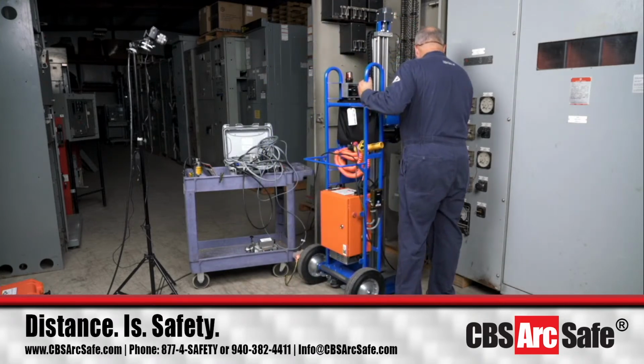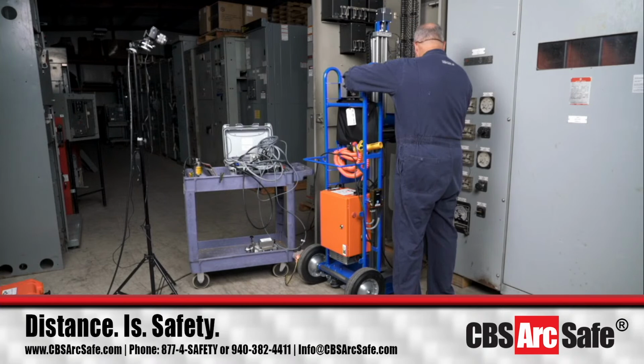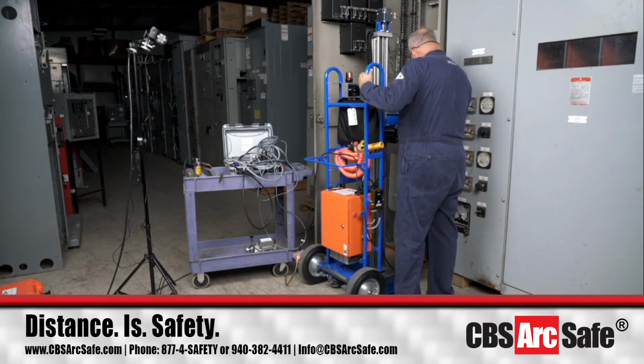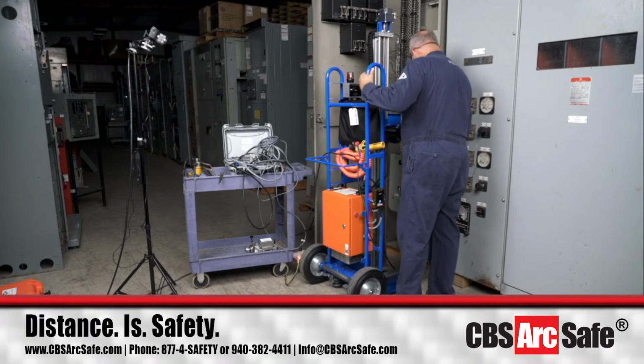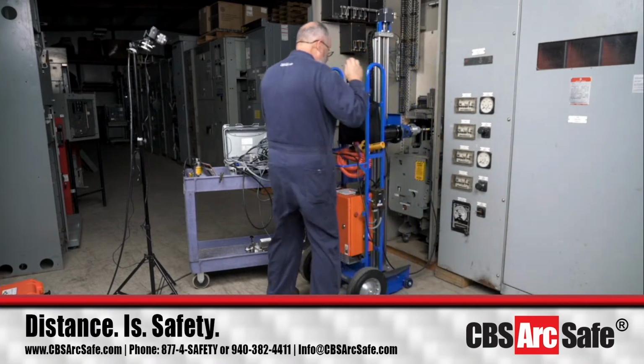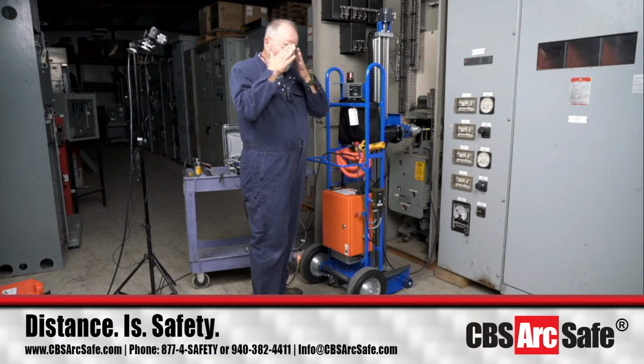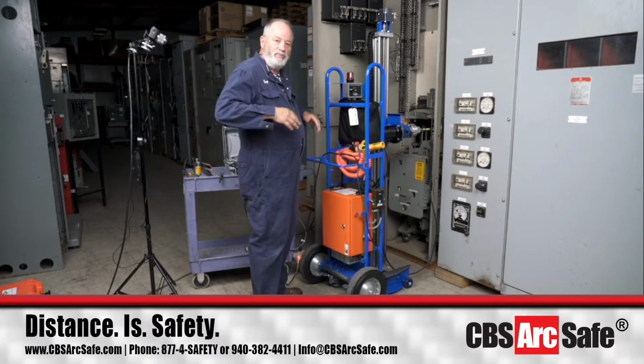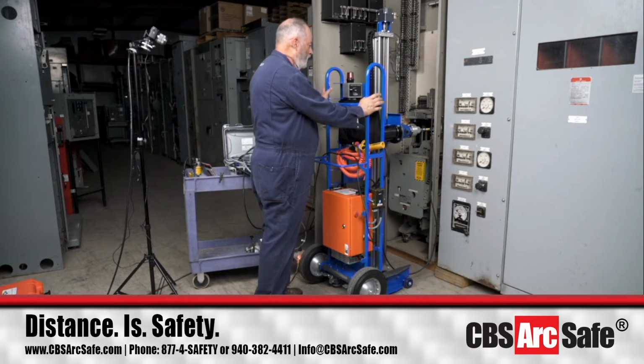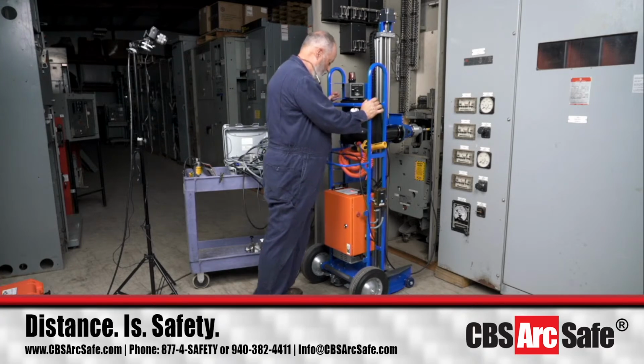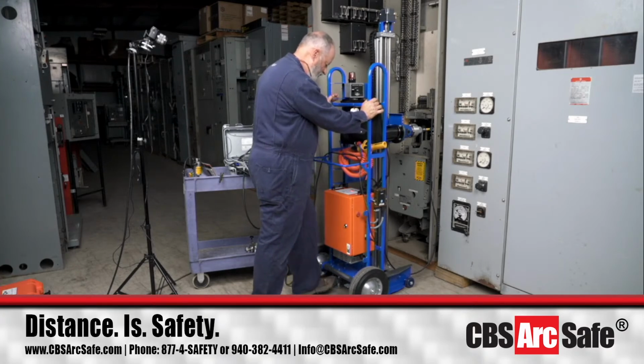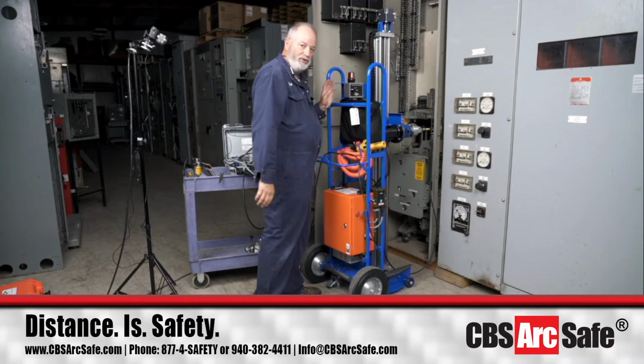Okay, go down just to here, come forward, break off. All right, now, whenever we're racking a breaker like this with the RS1, we don't let it just possibly go back and forth or anywhere. If it's a stationary racking mechanism like this, we'll push it forward, and we're going to lock our foot latches down so the RS1 becomes a stationary unit.